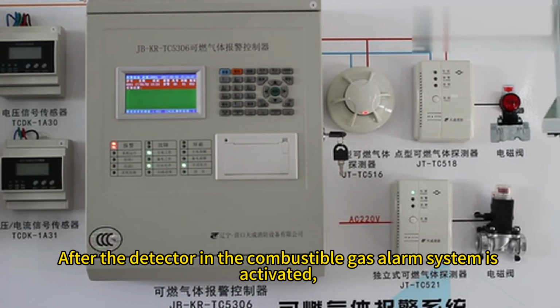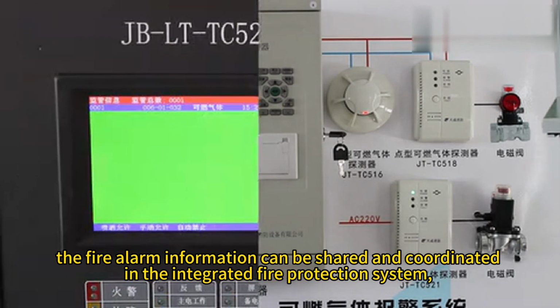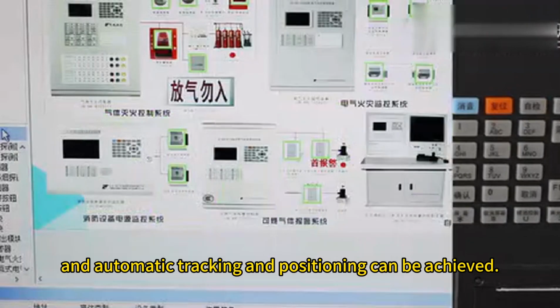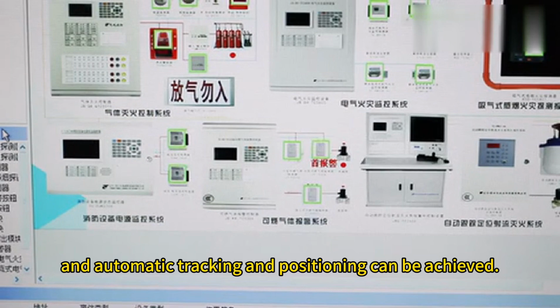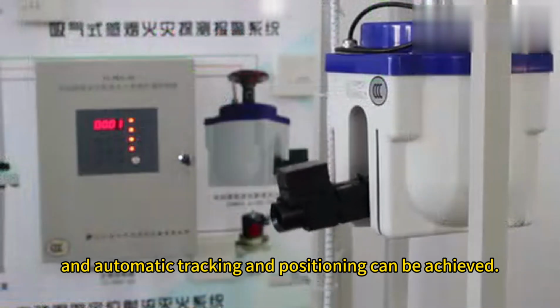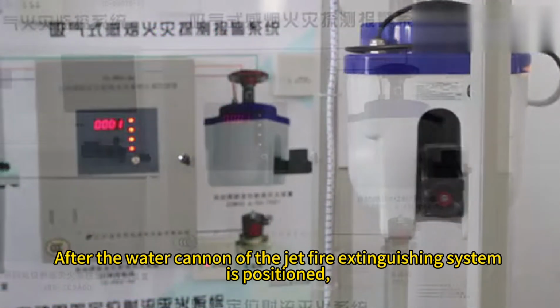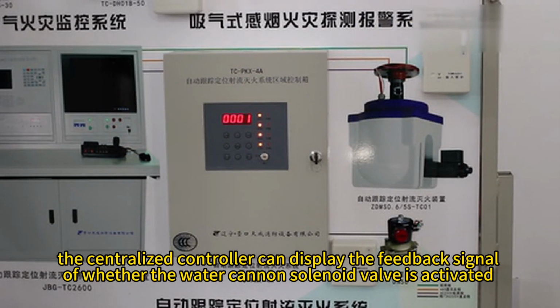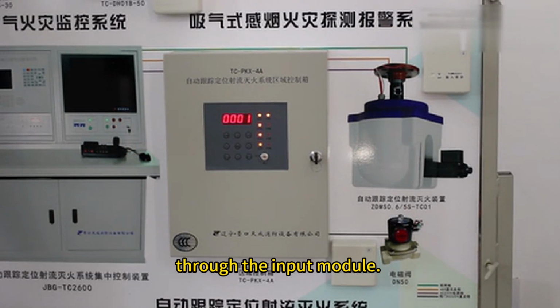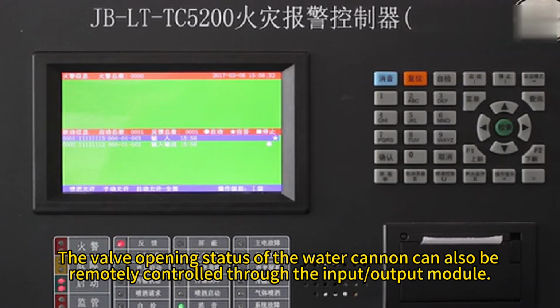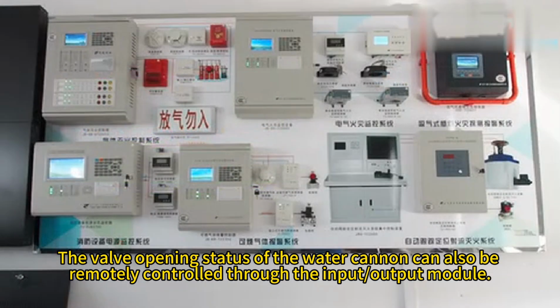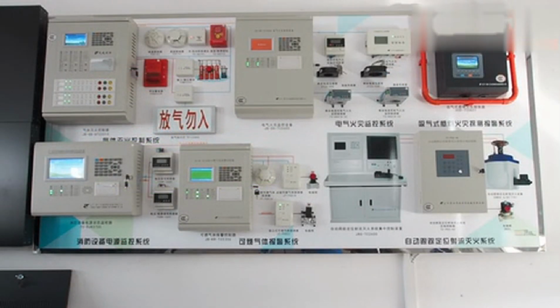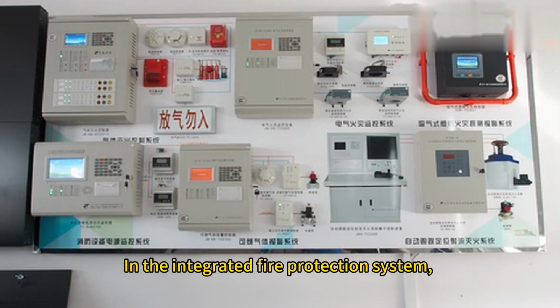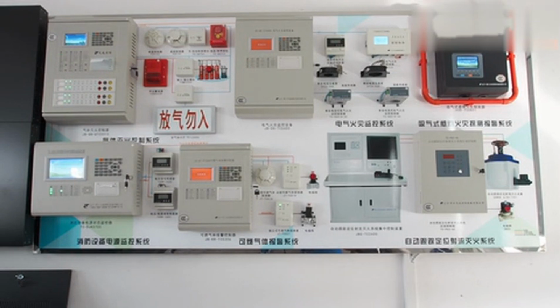The fire alarm information can be shared and coordinated in the integrated fire protection system, and automatic tracking and positioning can be achieved after the water cannon of the jet fire extinguishing system is positioned. The centralized controller can display the feedback signal of whether the water cannon solenoid valve is activated through the input module. The valve opening status of the water cannon can also be remotely controlled through the input-output module.